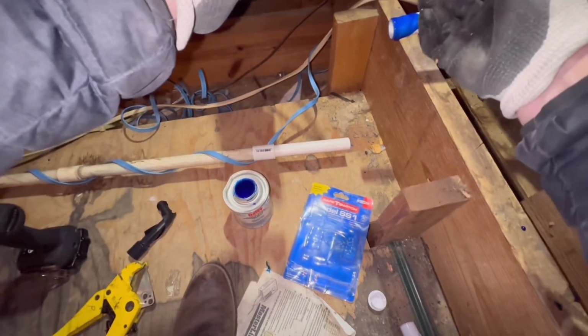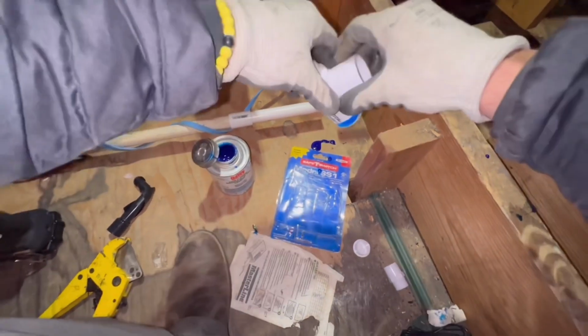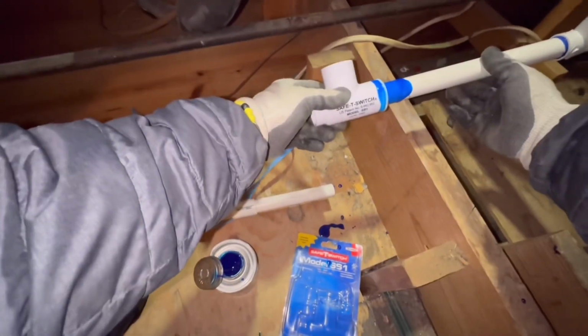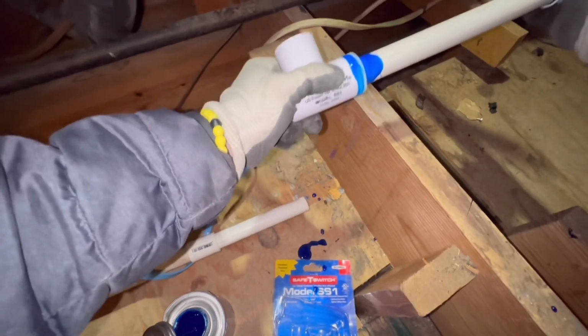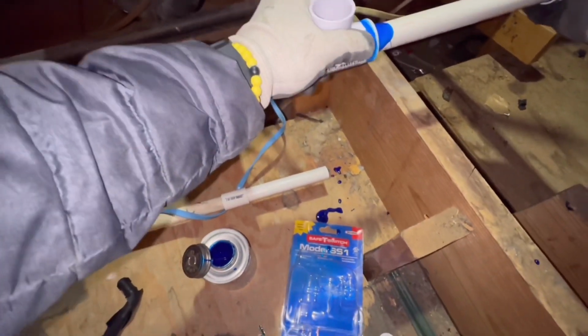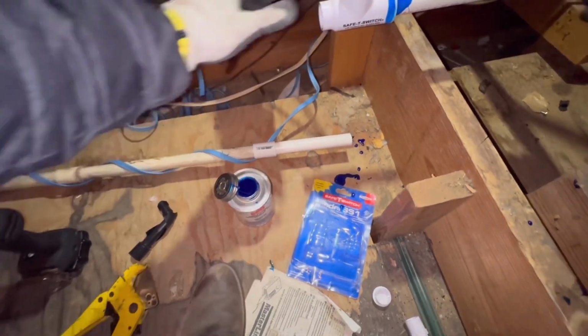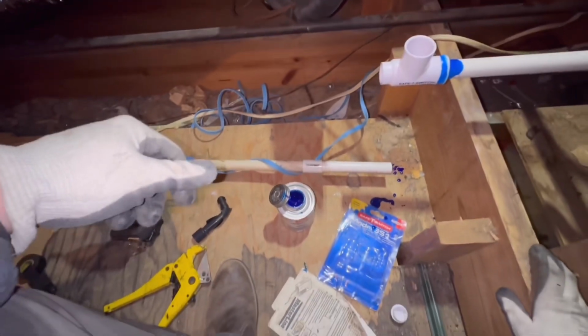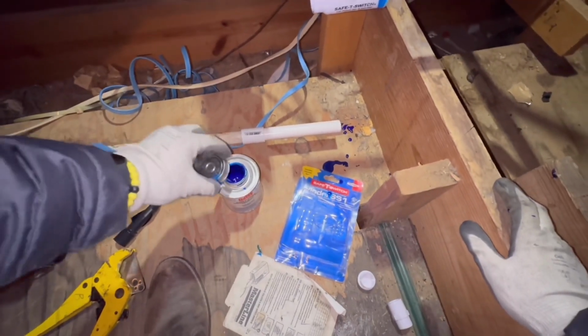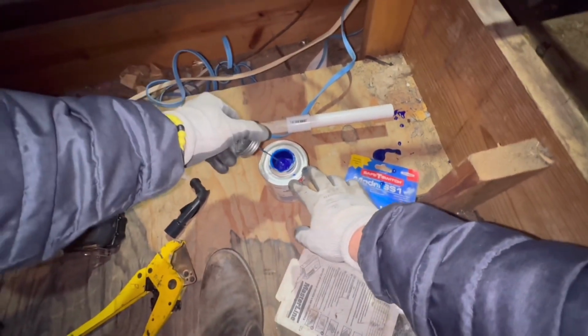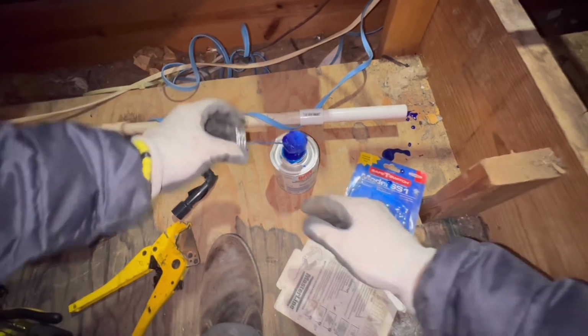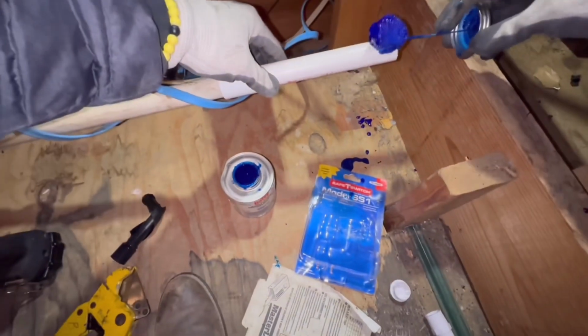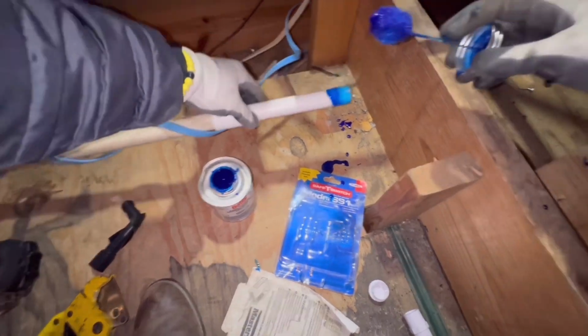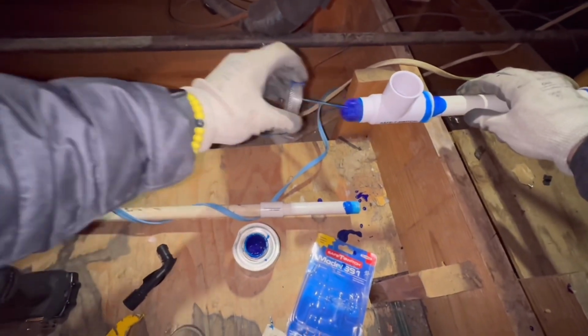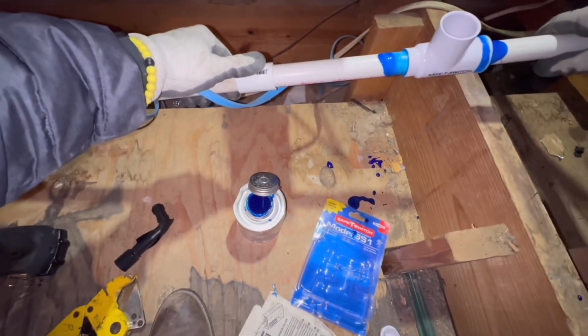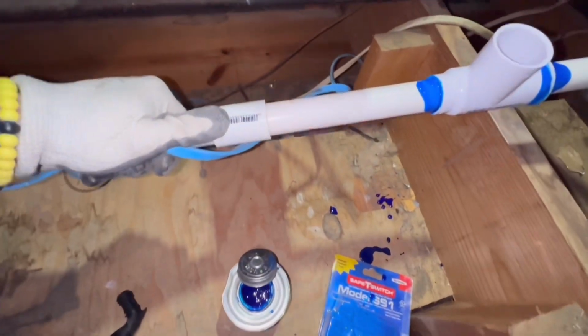It's very important when using PVC glue that once you stick the pipe into the fitting, you rotate it at least 90 degrees. If you notice, I started 90 degrees from where I wanted the pipe to end and rotated it. What this does is it provides a weld, creating a nice watertight seal. Now when you get to the very last connection like this one, obviously you're not going to be able to twist it, so just make sure it's all the way in the pipe. Very important that when applying the glue, you always put it on both pieces, the male and the female, like so. On this very last connection, the goal is make sure the pipe pushes all the way into the fitting, like so.